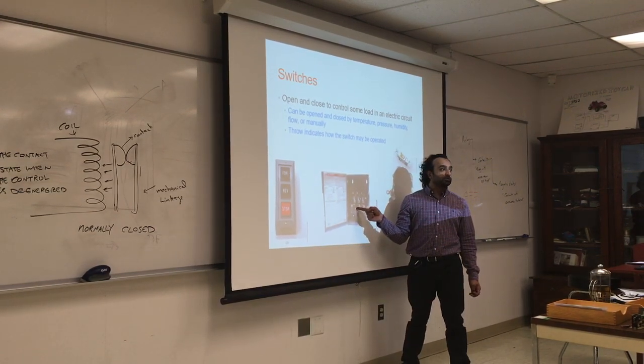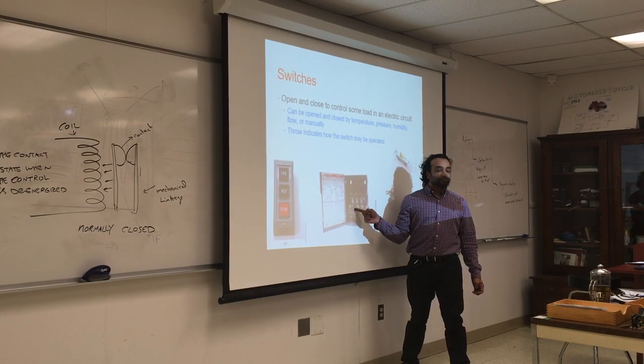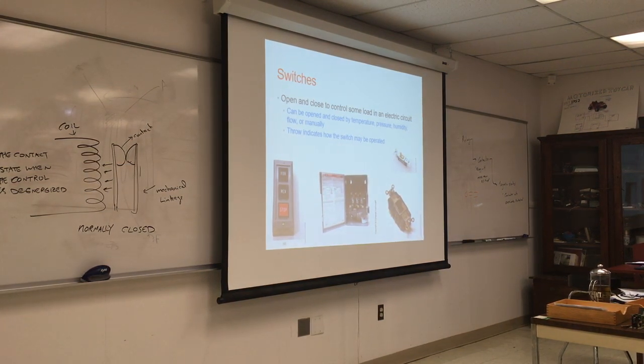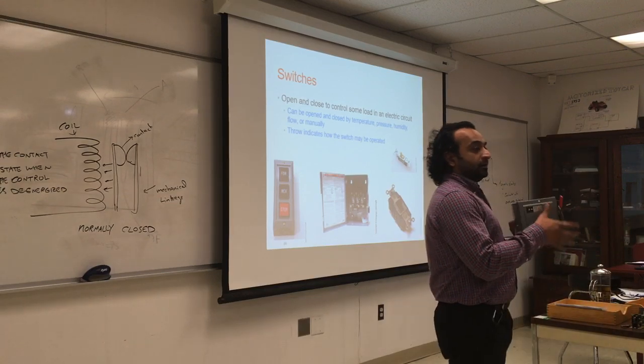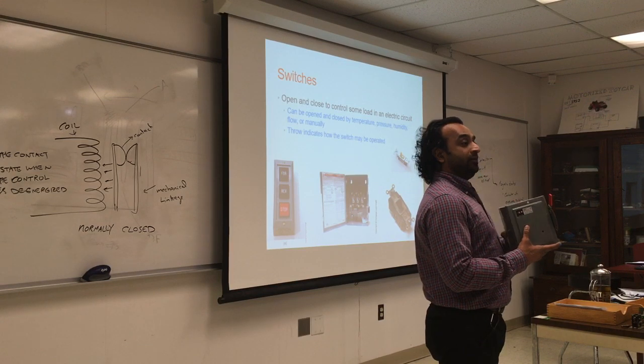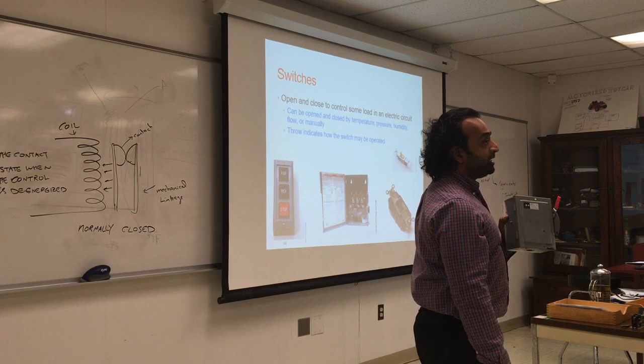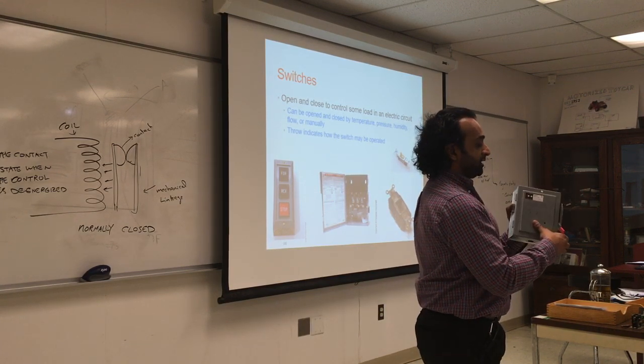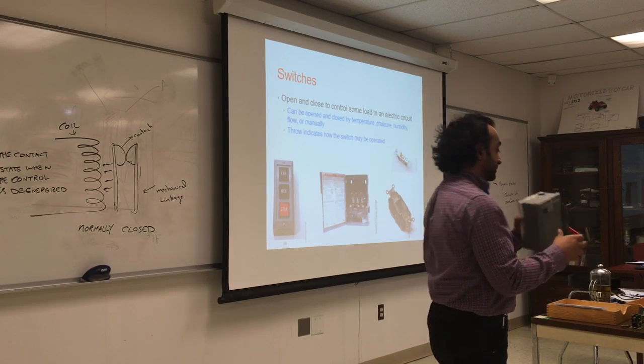This is a disconnect switch for big power, used for a lot of manual work, and they have a lock. I showed you what it looks like - that's a disconnect switch. Every piece of equipment you install outside the house must have a disconnect switch right next to it. Why? If anything goes wrong with it, somebody has to be able to disconnect the equipment right away instead of having to go to the power panel. So this is a big disconnect switch - it opens up when it's off, and you can lock it so nobody will turn it on. Disconnect switch.